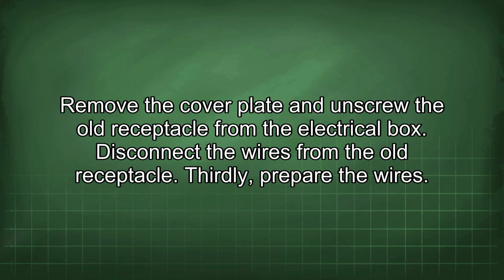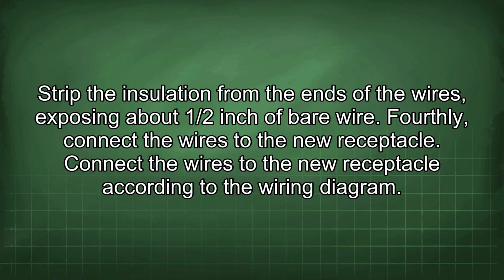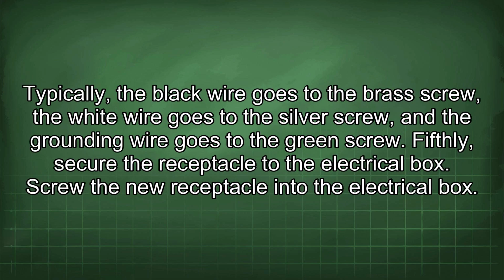Thirdly, prepare the wires. Strip the insulation from the ends of the wires, exposing about 1/2 inch of bare wire. Fourthly, connect the wires to the new receptacle according to the wiring diagram. Typically, the black wire goes to the brass screw, the white wire goes to the silver screw, and the grounding wire goes to the green screw.